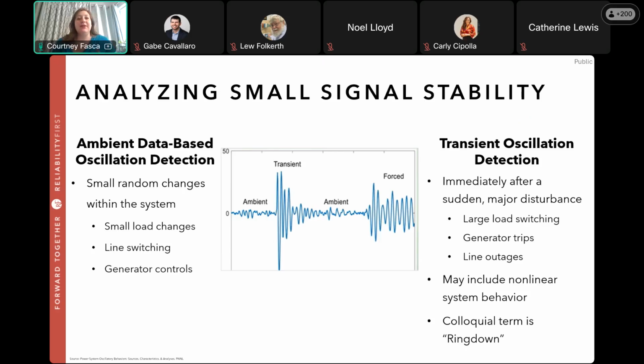So ambient data-based oscillation detection analyzes the small signal stability in normal operating conditions without any requirement for a disturbance to happen. So that would basically be the continuous monitoring method. You don't need a full-on disturbance to kickstart the detection, and it's great at tracking slow, creeping changes in the system conditions. However, this does mean that we lose out on accuracy, and it requires longer data windows. So think of it as 10 to 20 minute windows you now have to analyze. And as you can guess, it's also more sensitive to noise.